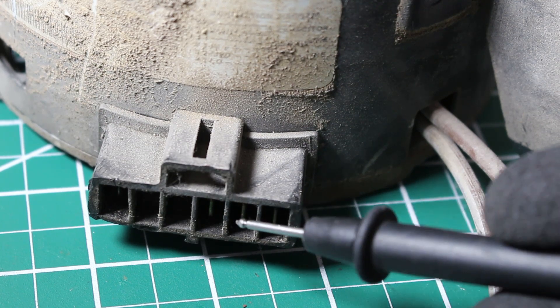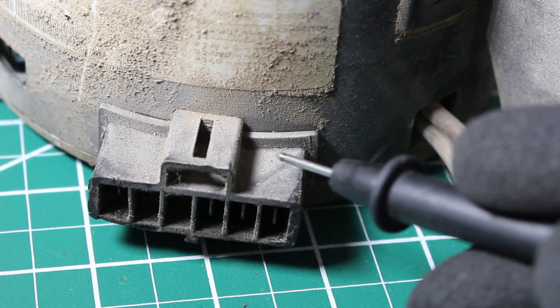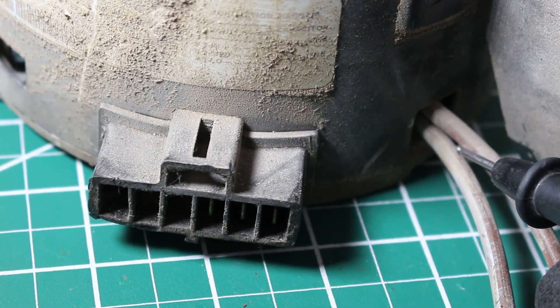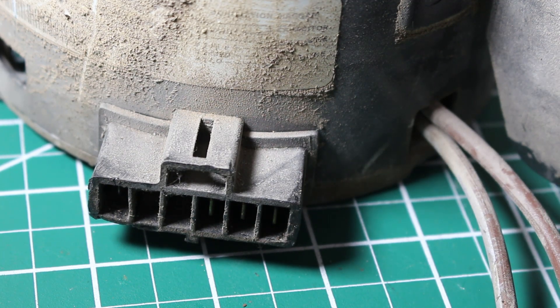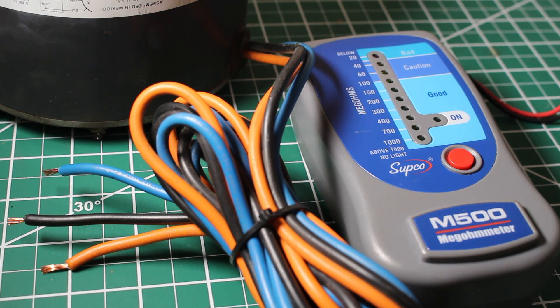For some motors you might be able to remove all the wires, and for others you might have a mix of both — some wires that can be removed and some that cannot. The whole goal is to isolate it as much as you can. Before using a megohmmeter please understand exactly what you're doing — this video is for professionals only, as we are applying 500 volts to this motor. Safety first.